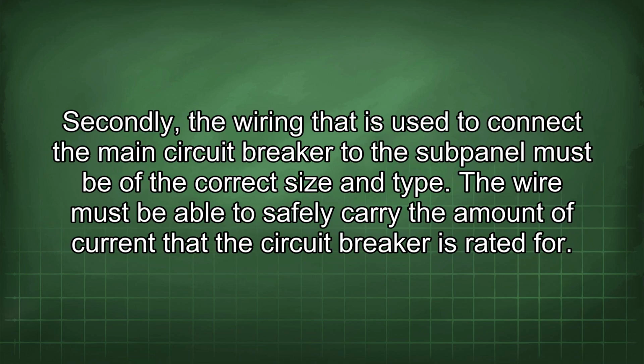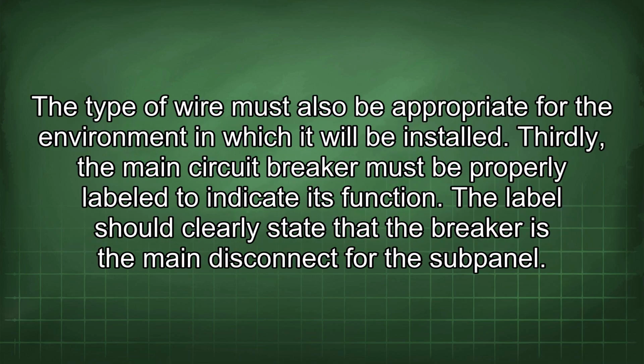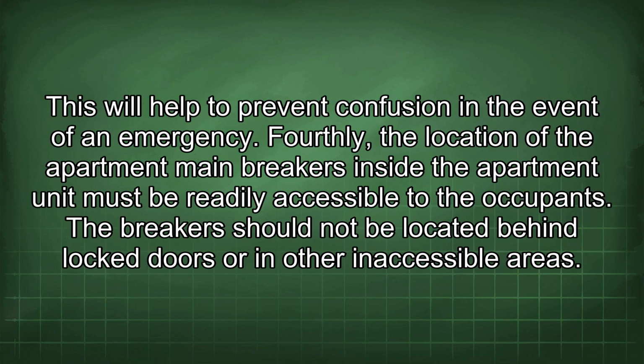Secondly, the wiring that is used to connect the main circuit breaker to the subpanel must be of the correct size and type. The wire must be able to safely carry the amount of current that the circuit breaker is rated for. The type of wire must also be appropriate for the environment in which it will be installed. Thirdly, the main circuit breaker must be properly labeled to indicate its function. The label should clearly state that the breaker is the main disconnect for the subpanel. This will help to prevent confusion in the event of an emergency.